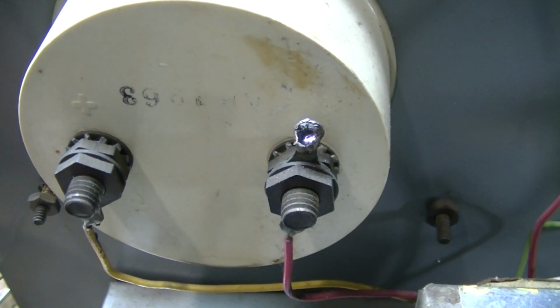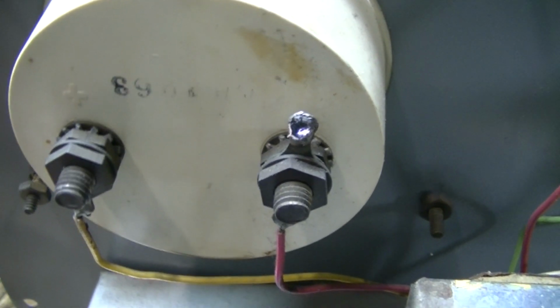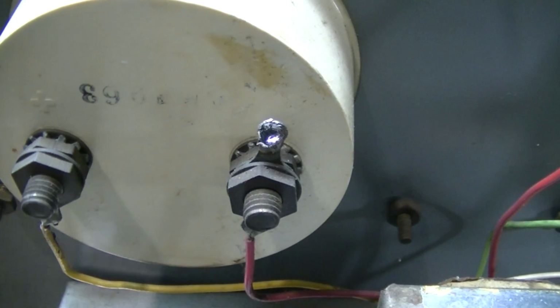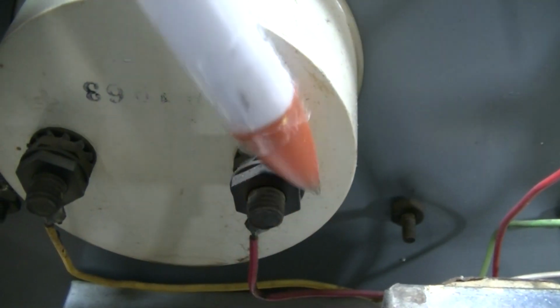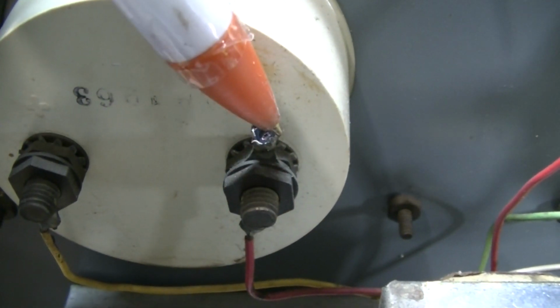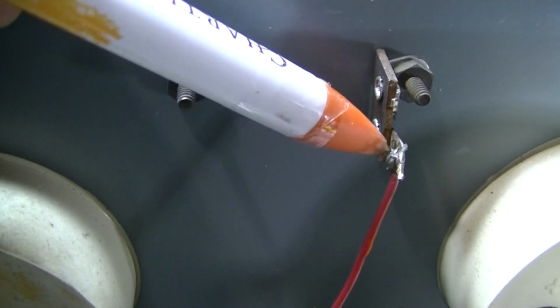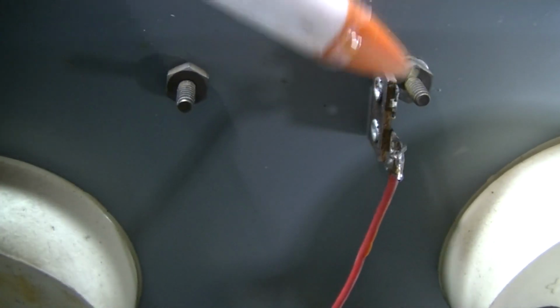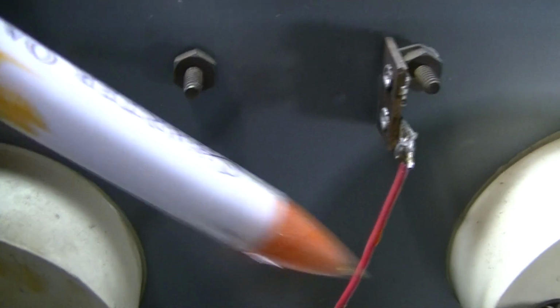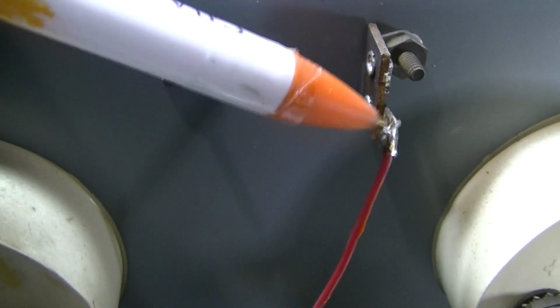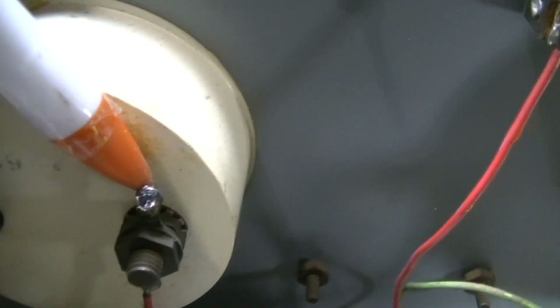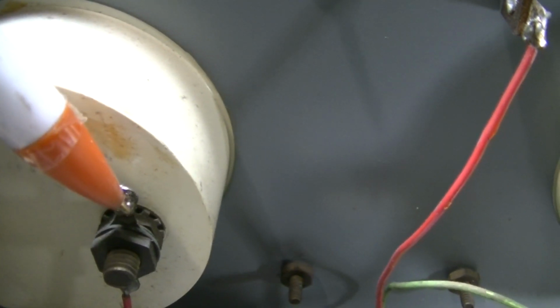This is the back of the milliamp meter, and it was tied right here. It was soldered here, and it went to this terminal up here. And it was kind of a loose connection. Of course, the screw was loose too, like everything else here. But the connection was not soldered very good, so that has to be redone and probably put that back in.